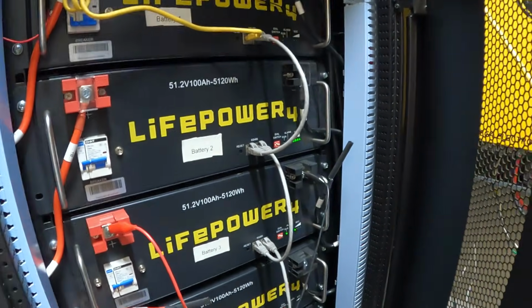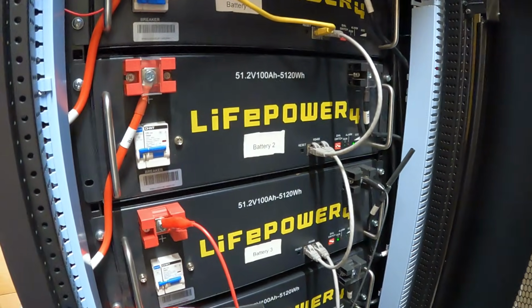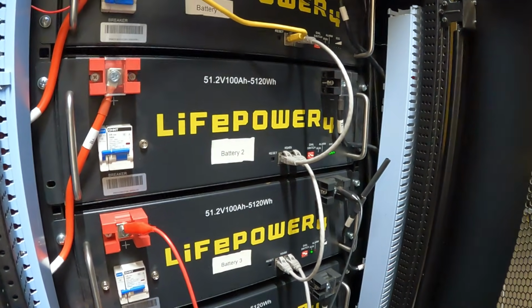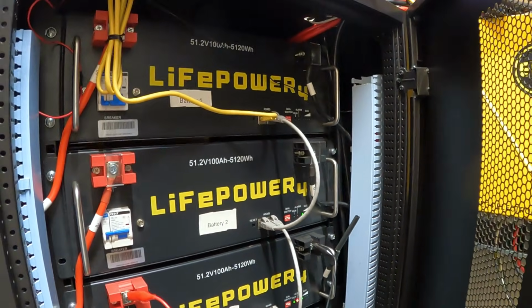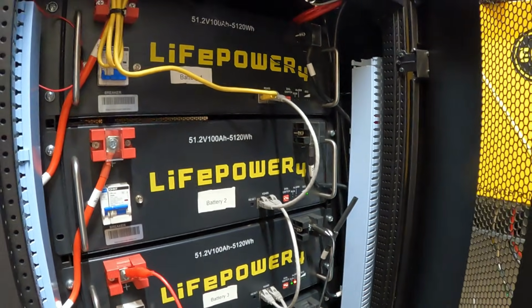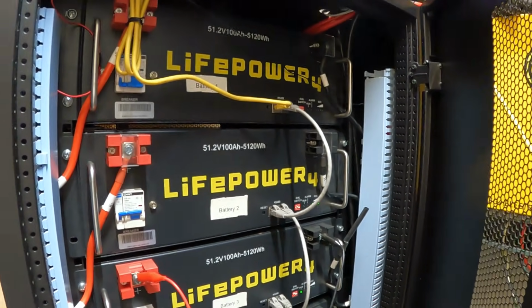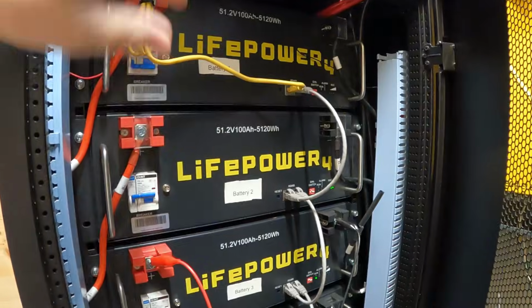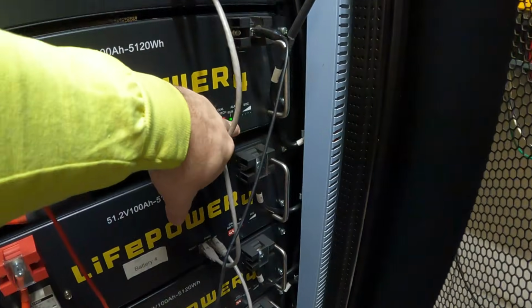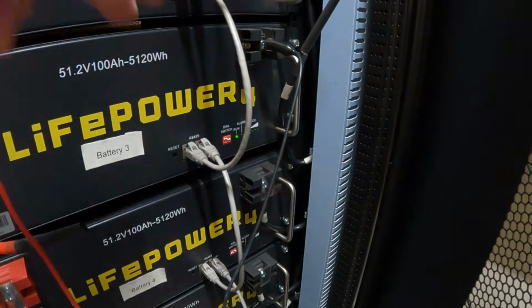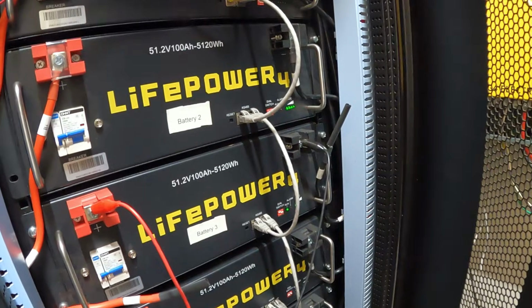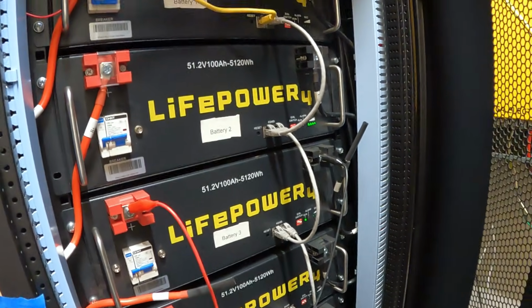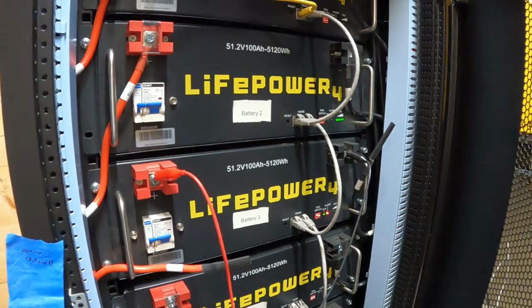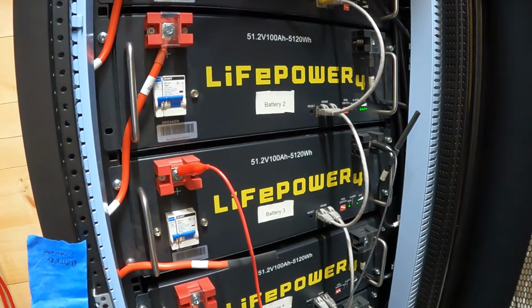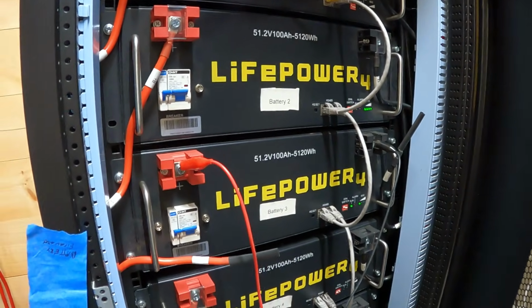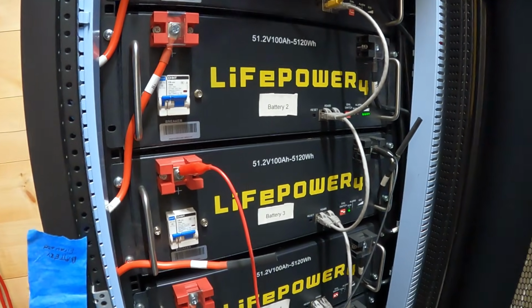So what I had was 4 out of 6 batteries shut themselves off with a combination of low cell voltage, so at least one cell in the pack got too low that it shut off, and you'll see a red light on this one, the alarm light right there. And 3 or 4 of them also got cold enough that the low temperature sensor, one of the thermometers, was triggered, and so they were off for that.